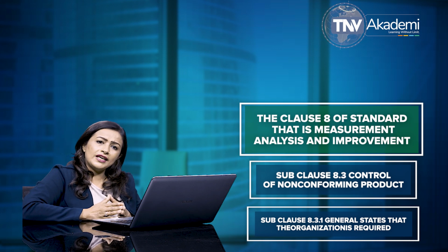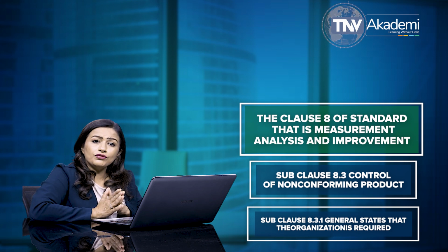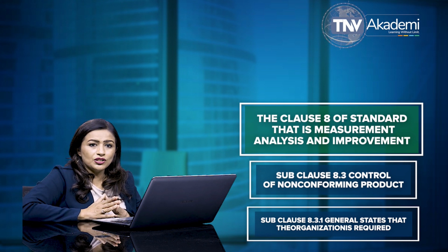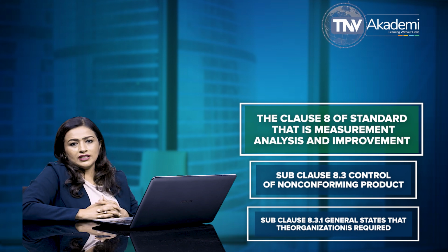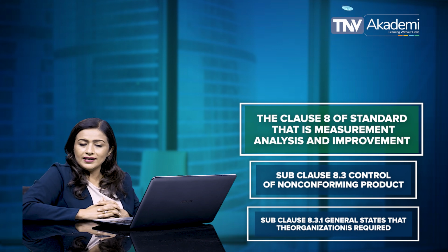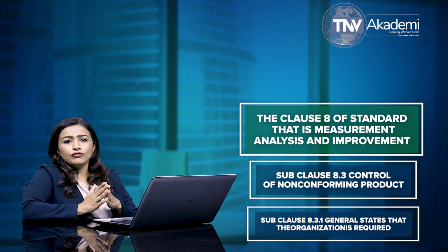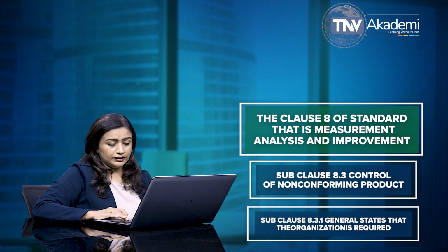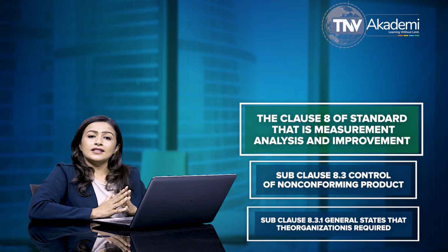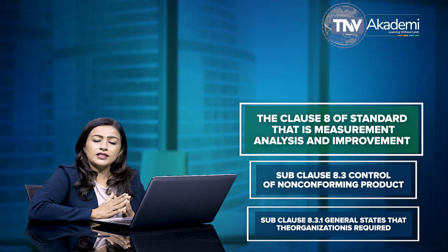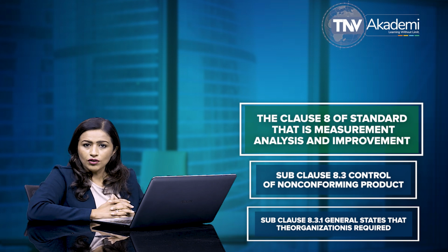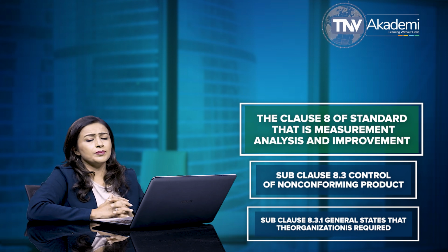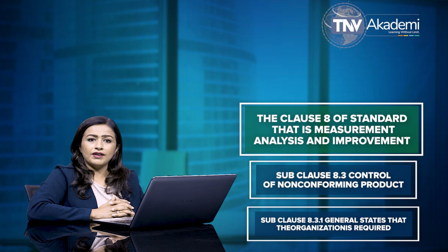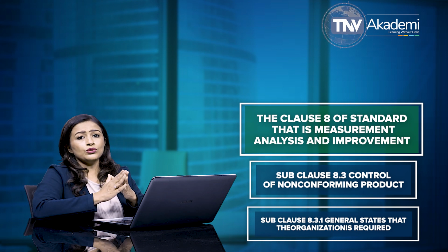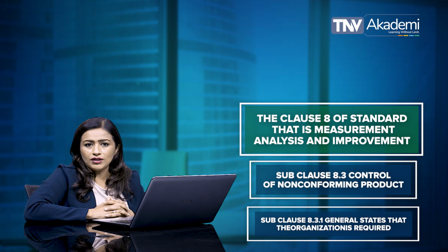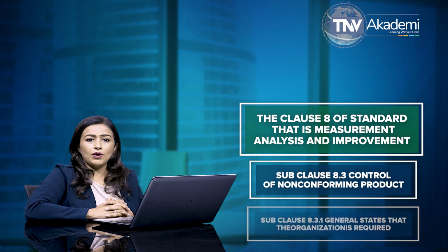As per this subclause 8.3.1, the evaluation of non-conformity must include a determination of the need for an investigation and notification of any external party responsible for the non-conformity. Further, this subclause states that organization is required to maintain the records of the nature of the nonconformities and any subsequent action taken, including the evaluation. Organization must also maintain any investigation and the rationale for decisions to meet the requirements of the standard.